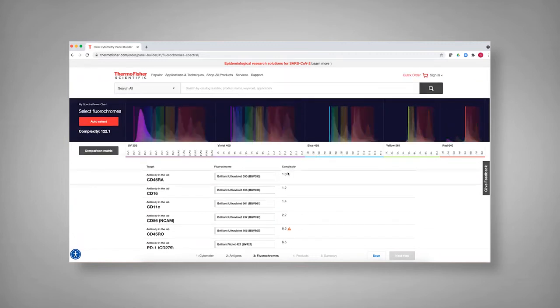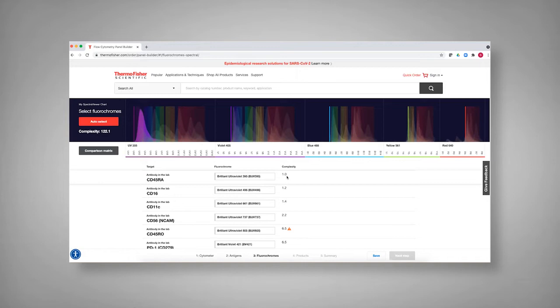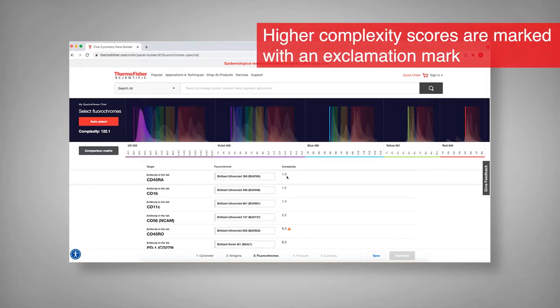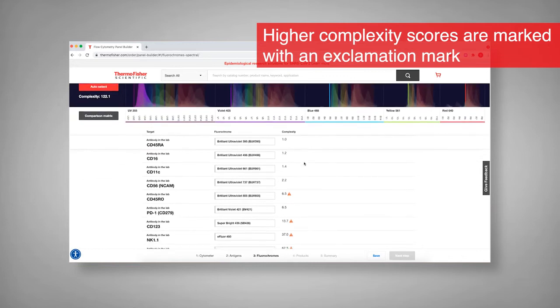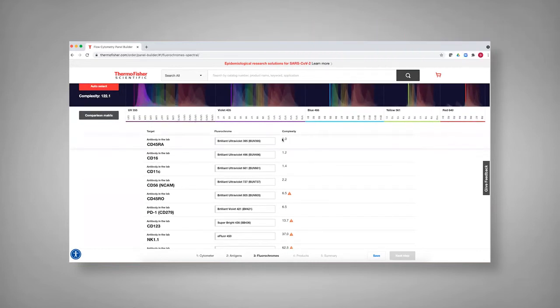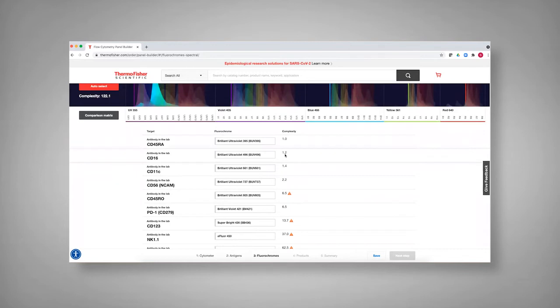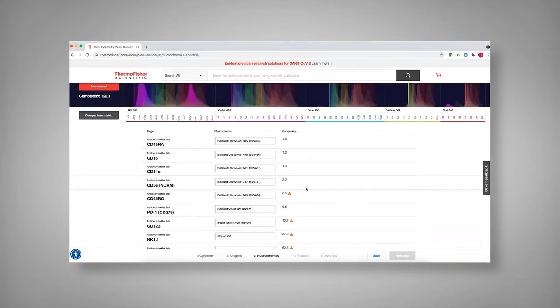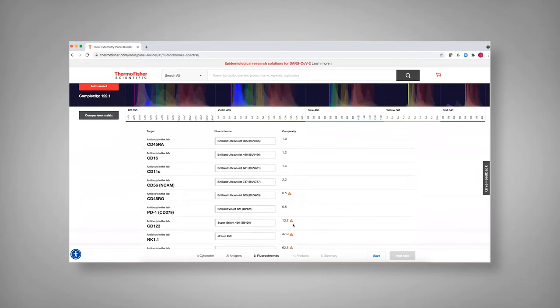And so as you go through and look at the panel, there's a few things I want to draw your attention to. The first one is to look at this complexity score. And this is being calculated as you go throughout the panel. So the complexity is considered to increase as you add each one of these. And this mimics what has been done with the Bigfoot software for the spectral sorter. You can see that as you add some of these with the colors, the complexity is not increasing that much on a spectral instrument. And then there are others where this actually increases more greatly. So the first place where you see a pretty large jump is with this area with BV 421.